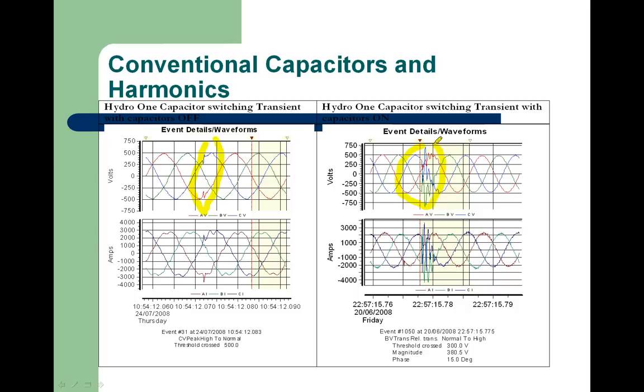So here, this is the voltage here. We see a very, very high momentary voltage rise and ring wave. And this is basically a resonance between the utility and internal capacitors in a facility. This is not only just in power factor correction capacitors. This also could be literally in small capacitors in variable frequency drives, computers, anything that has a small capacitor in it. The bottom here is the current, and although it's very momentary, you can see here where this is a peak current. Basically went from a little over 2,000 amps peak to over 4,000 amps peak. In some cases where you have variable frequency drives, you can have some nuisance tripping where they will trip offline in cases like this. So utilizing a harmonic filtered capacitor bank, the result would be something more like on this side here.